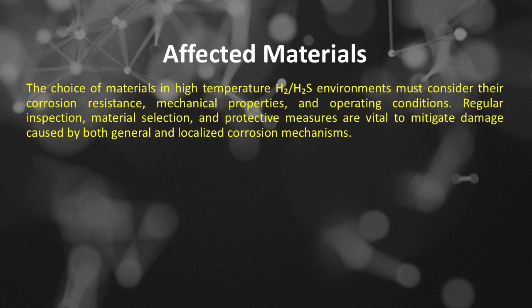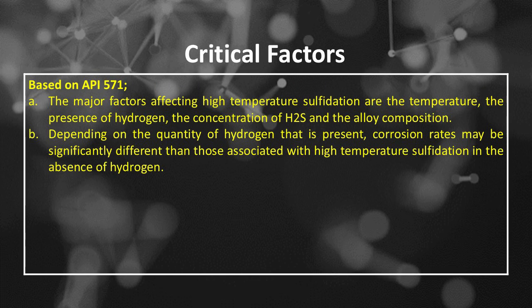The choice of materials in high-temperature hydrogen or H2 and hydrogen sulfide or H₂S environments must consider their corrosion resistance, mechanical properties, and operating conditions. Regular inspection, material selection, and protective measures are vital to mitigate damage caused by both general and localized corrosion mechanisms. High-temperature hydrogen or H2 and hydrogen sulfide or H₂S corrosion critical factors based on API 571.